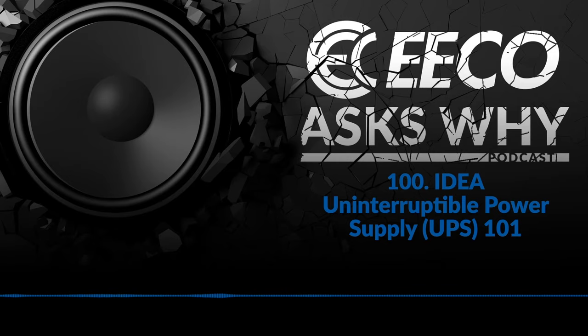On some of the smaller UPS systems where the battery is internal, if you have a lithium-ion battery, there's really no maintenance there at all. You're going to need to change that lithium-ion battery within 7 to 10 years typically. If you're in a dirty power environment where you're always having voltage sags, brownouts, or blackouts, and using that UPS a lot, that battery's going to need to be changed before that 7 to 10 years, typically.